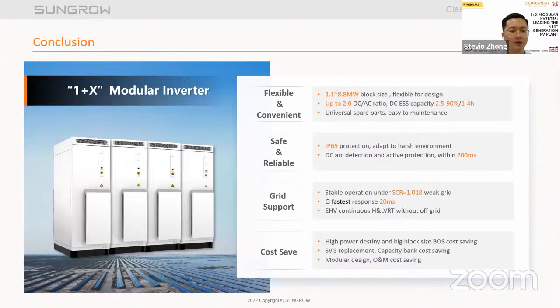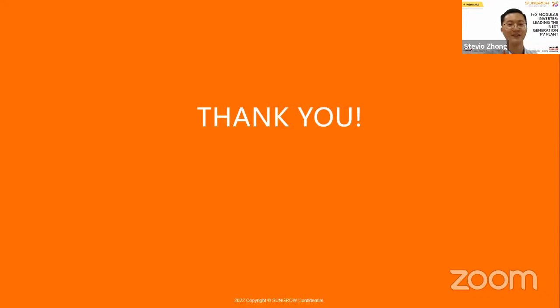There are a few things I would like you to take away from this presentation. 1.1 to 8.8 megawatt block size, the flexible design, and ESS capacity enable the 1+X modular inverter to be more flexible and convenient. IP65 protection and real-time DC arc detection guarantee the safety and reliability of this product. Stable operation and faster response help the inverter to support the grid. The high power density, big block size, and SVG replacement make the product more cost saving for our developers. Thank you. That's all for this presentation.